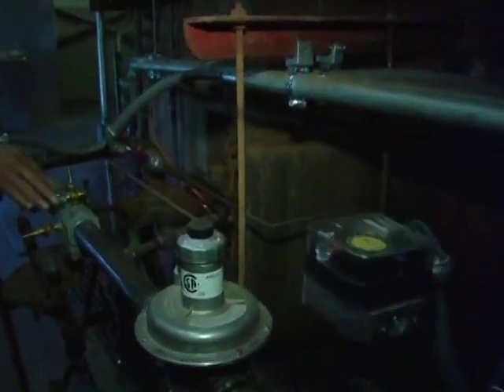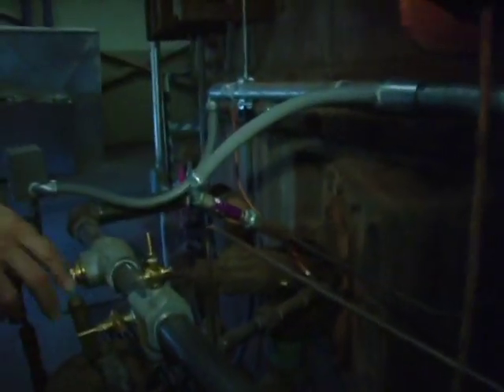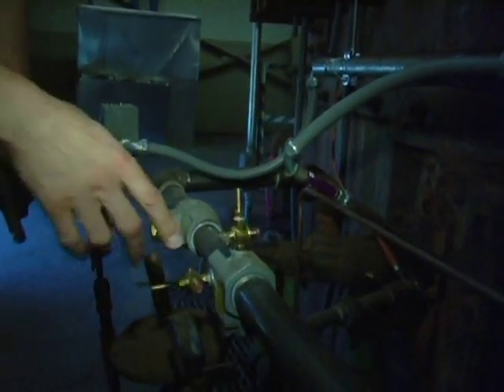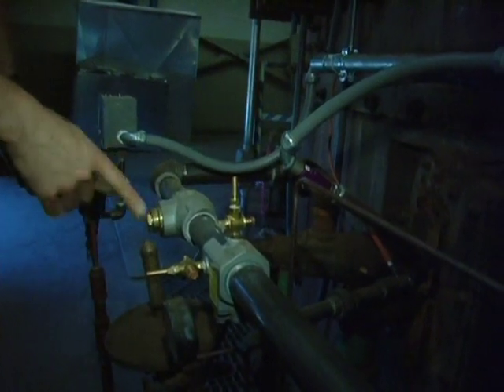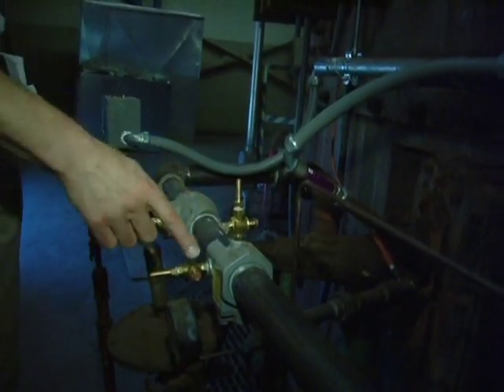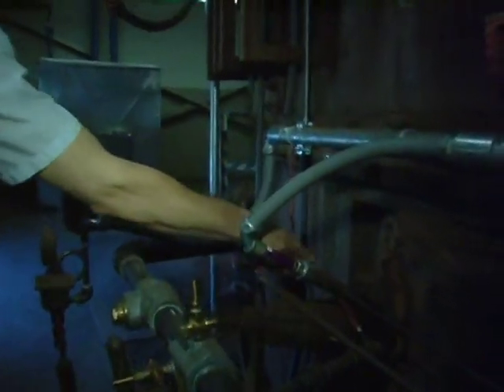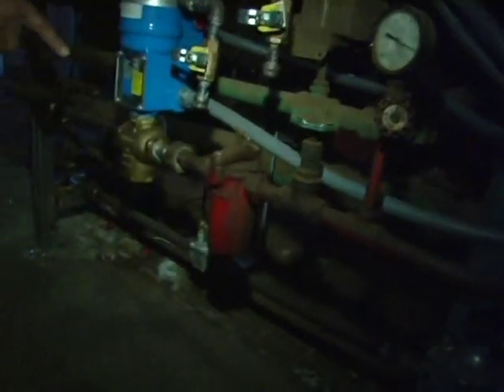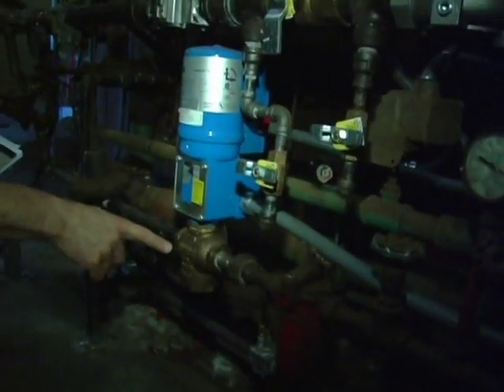And these devices here are for fine-tuning of the gas flow. The IFCO people will adjust these things. You don't have to worry about them, okay? They're just fine-tuning. The gas comes through, goes into the burner here, okay? So that's your gas. Your oil comes in down over here. Oil line, these are dual fuel burners, of course. Oil comes up in this line here, the red line, comes over here, small pipe. Filter, there's a gauge, there's a shutoff. This is your automatic shutoff valve now for your oil, okay?